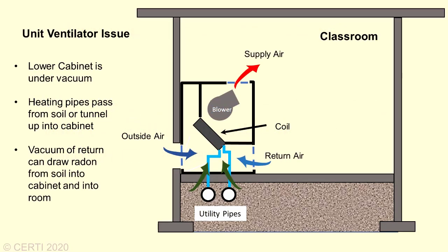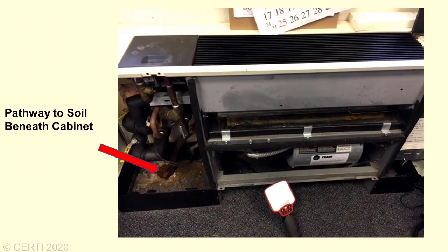A situation that is specific to unit ventilators is that the lower portion of the cabinet is the return air plenum where air is pulled from the room and reheated. There is a significant vacuum within this lower portion of the cabinet. It is also where heating pipes can enter from beneath the slab or from a utility tunnel located under the unit ventilators. If these floor penetrations are not sealed, the unit ventilator can literally mine radon through the gaps around the pipes and introduce it into the room. These penetrations should be well sealed, and the degree to which they are sealed can also cause room-to-room variations in radon levels.